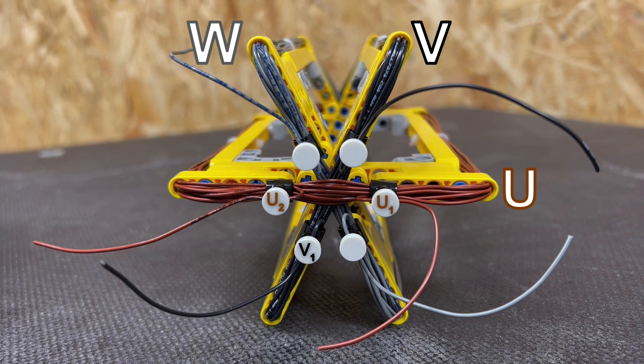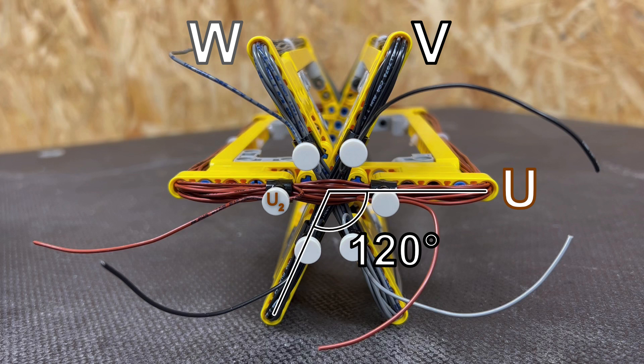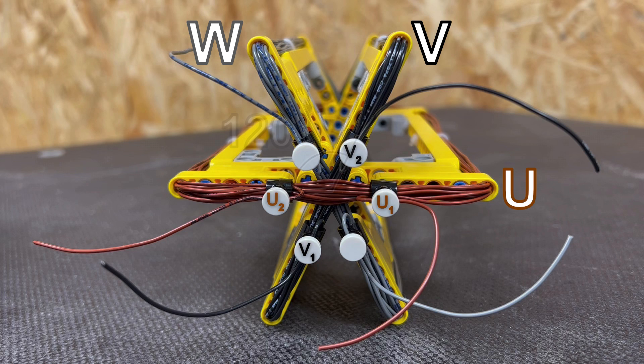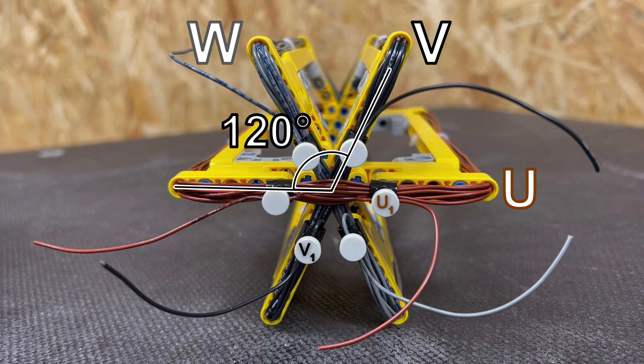This end will be V1. Notice that this end is offset by 120 degrees from U1 and the other end V2 is offset by 120 degrees from U2. And the same principle applies to the final winding with W1 here and W2 here.